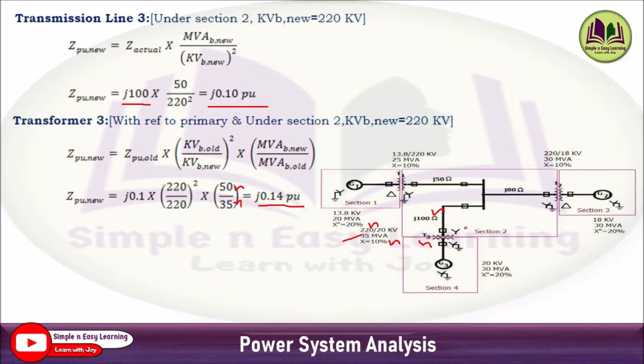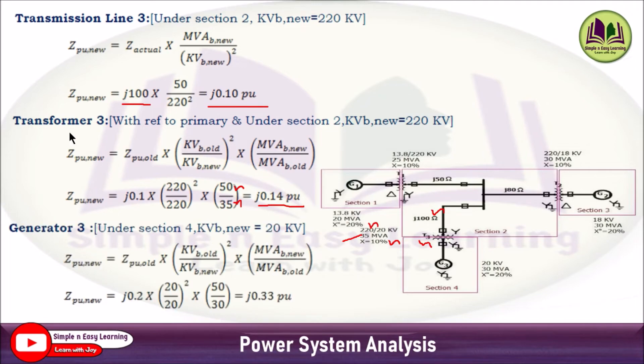Finally, for generator G3 in section 4 (base kV = 20 kV, rated 30 MVA, 20% reactance): Z_pu_new = j0.2 × (20/20)² × (50/30) = j0.33 per unit. We have now found the per unit impedance of all components and will draw the impedance and reactance diagram with all values substituted.